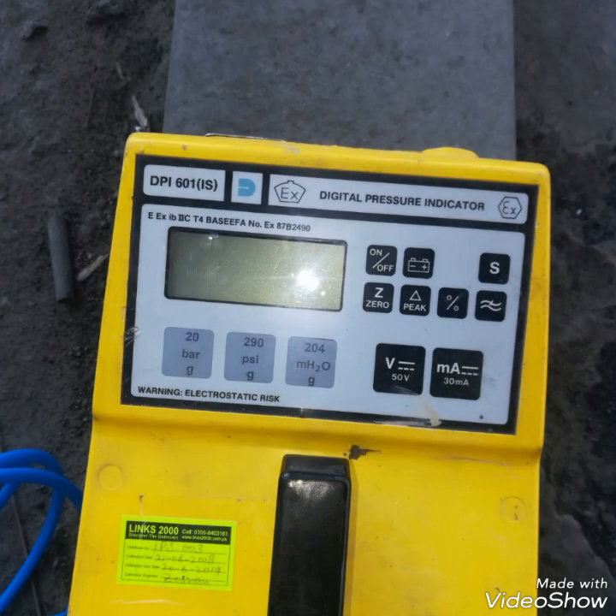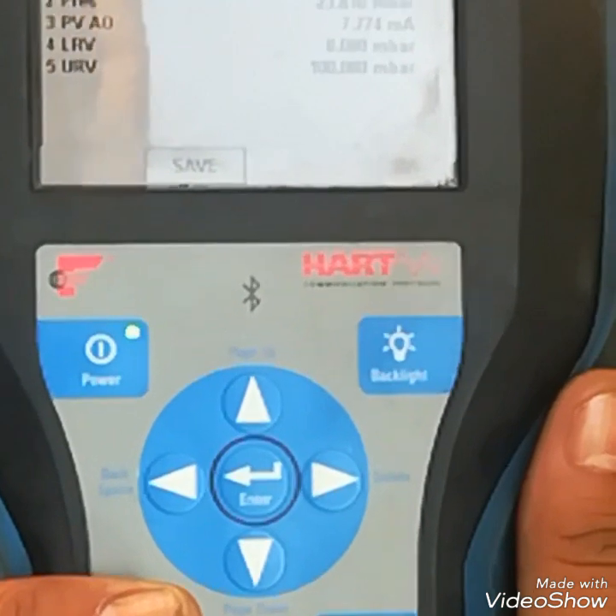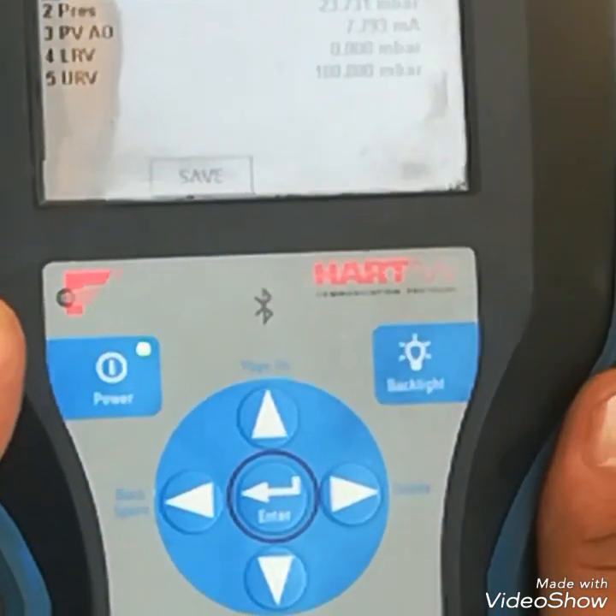Hello friends, how are you? You can see this is a Druck pressure source and digital indicator DPI 601. Here you can see a HART communicator 747, HART protocol. We will check the calibration of a pressure transmitter whose range is 0 to 100 mbar.